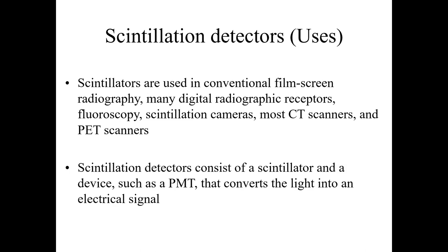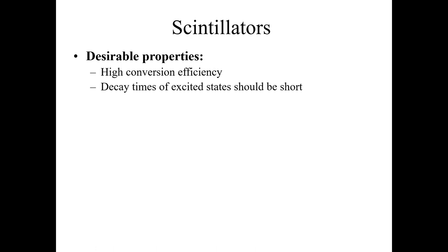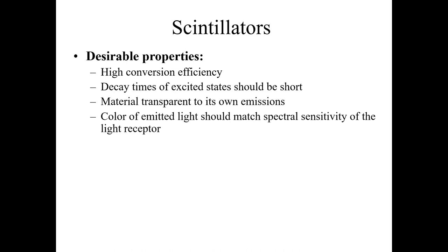Scintillation detectors consist of a scintillator and a device such as a photomultiplier tube (PMT) that converts light into an electrical signal. Some desirable properties of scintillators include high conversion efficiency, short decay time, and the material should be transparent to its own emissions. The color of the emitted light should also match the spectral sensitivity of the light receptor.